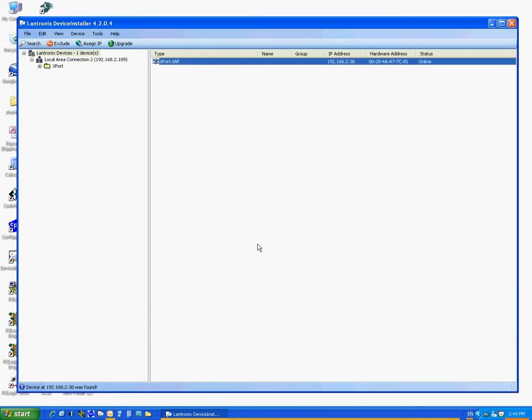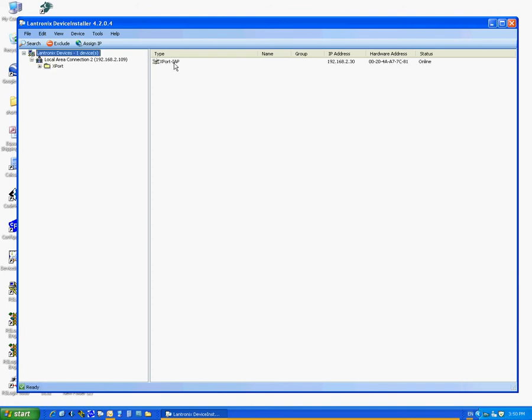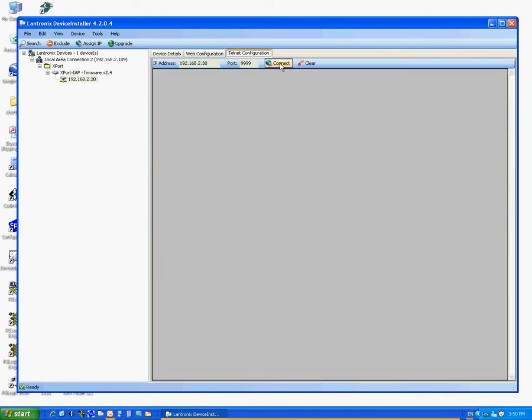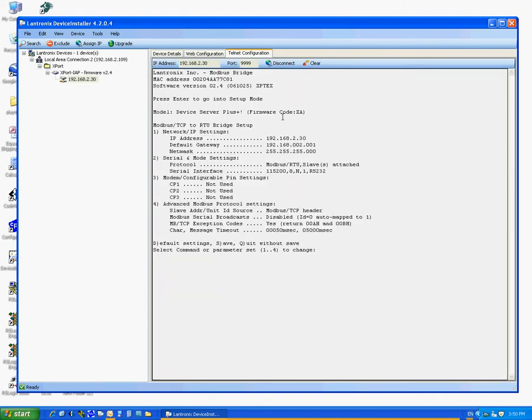Now that you have assigned the IP address, you need to set the internal Modbus serial setting using Telnet. To Telnet, double click on the unit under Type. Click on Telnet Configuration tab. Click on Connect. Once you see Press Enter to go into Setup Mode message, press Enter right away, do not wait.